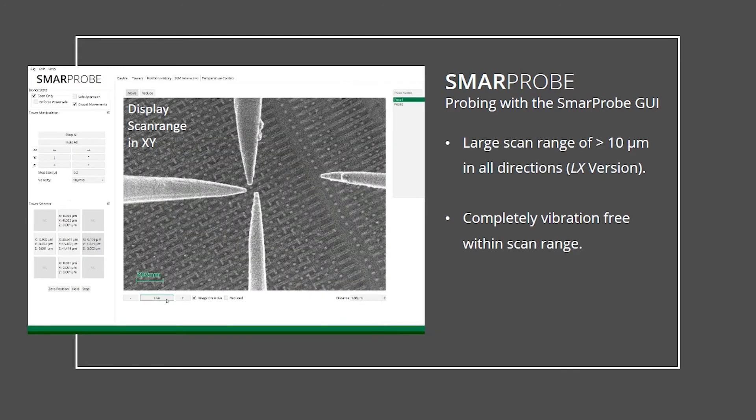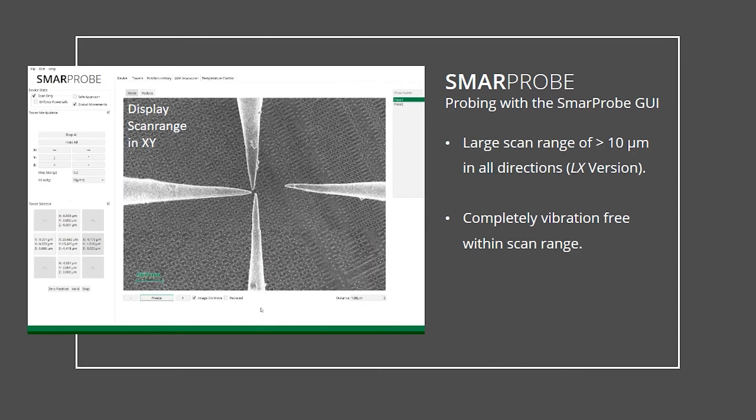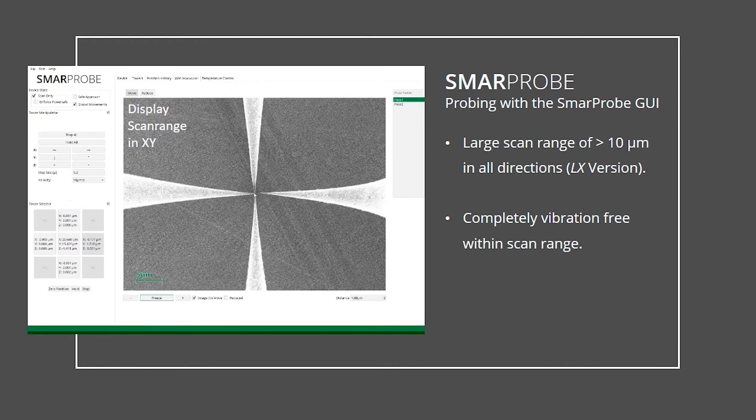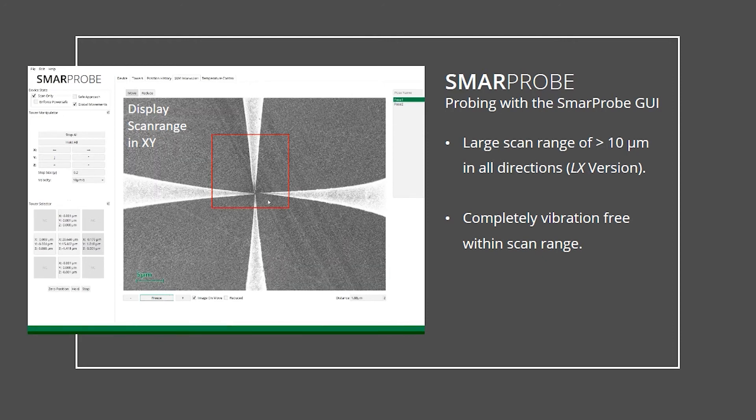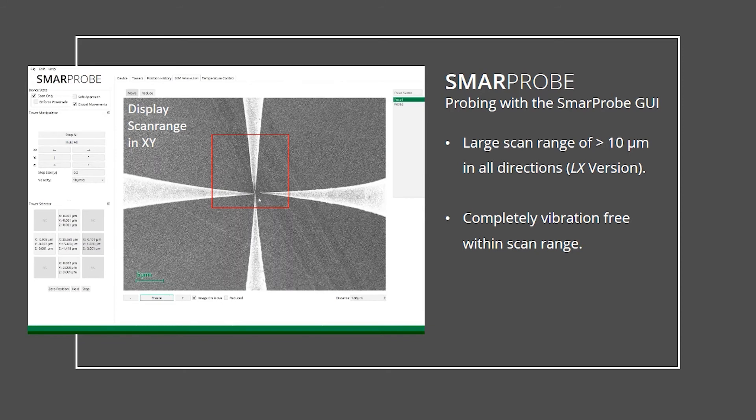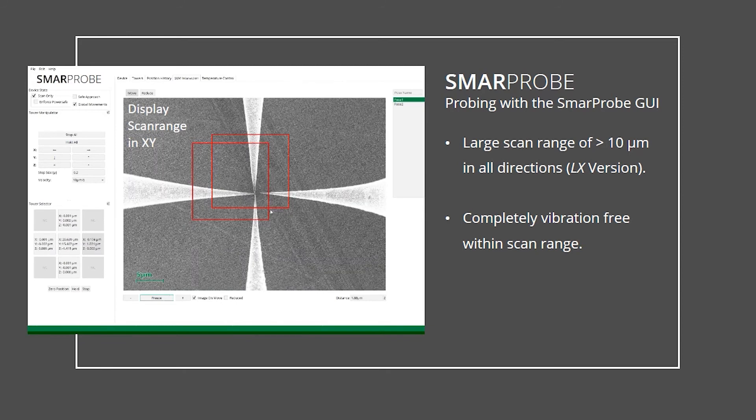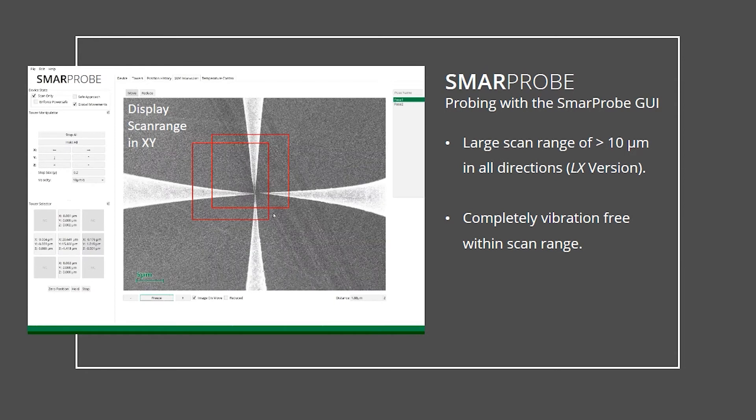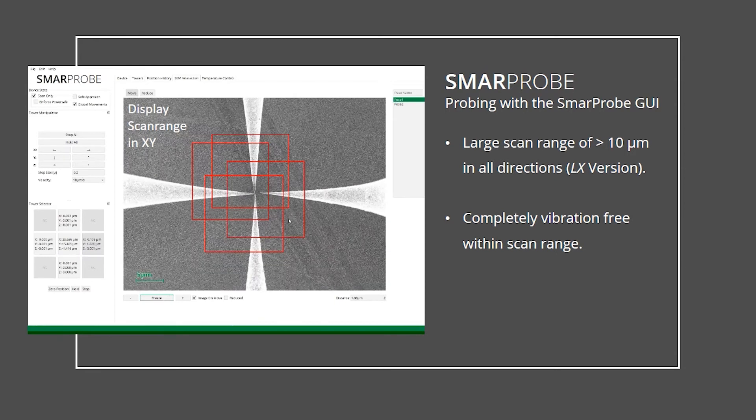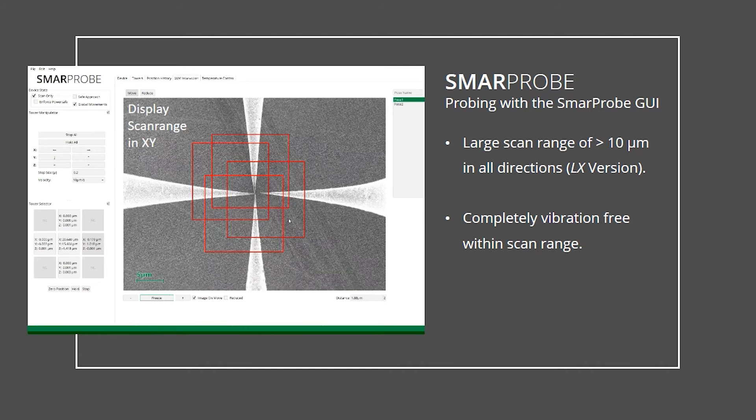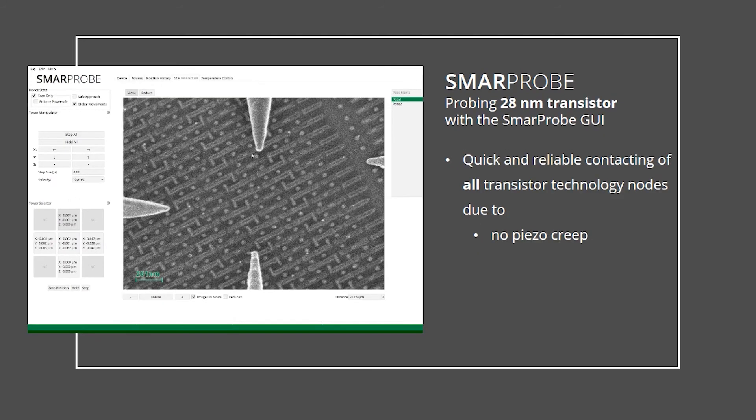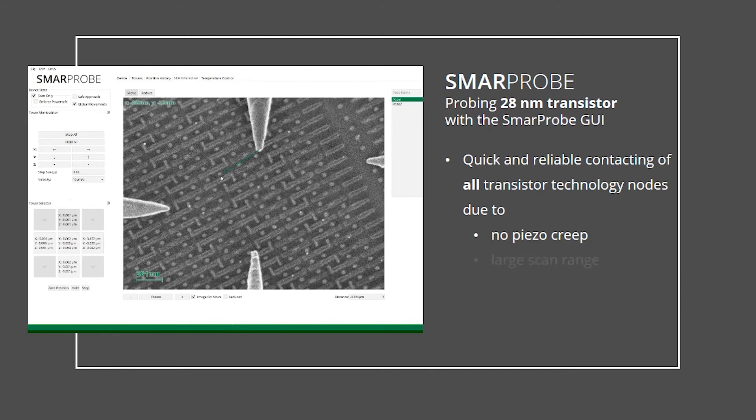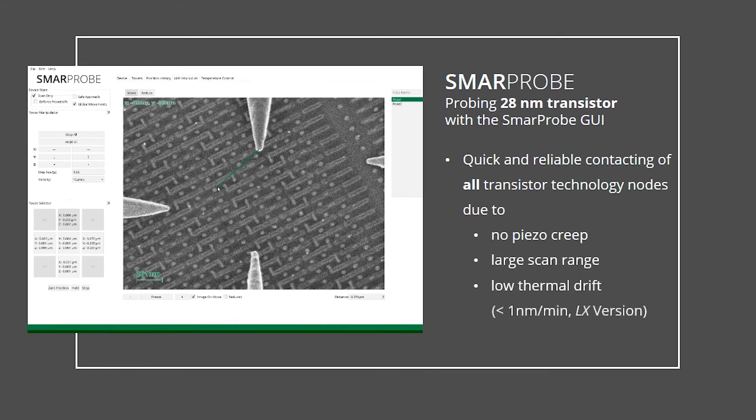The SmarProbe LX is equipped with unique hybrid positioners, which exhibit a scan range of above 10 micrometer. To ensure quick and safe nanoprobing, a large scan range is beneficial. The graphical user interface displays the scan range area within the image of the microscope. Manually contacting a transistor of the 28 nanometer technology node is shown in this video.